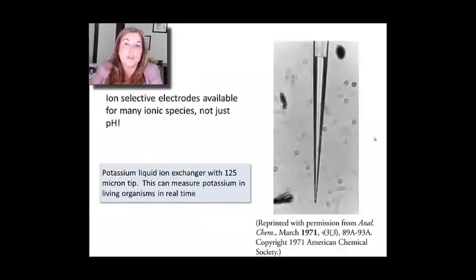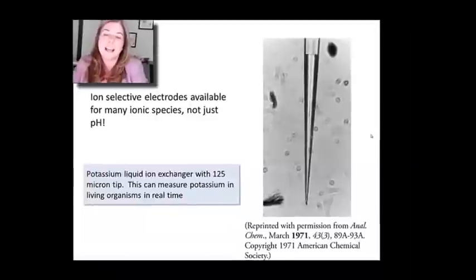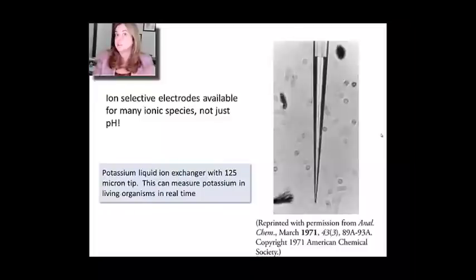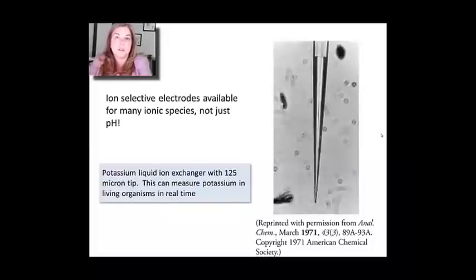Now, ion-selective electrodes, as I said, don't just have to be for pH. They can be for a lot of different things. In this case, this is a potassium ion exchange electrode, and it's very small. And so, that allows it to interact or measure, for example, potassium through tissue at very specific places. It's a little too big to do the single-cell measurements like I showed you in the last lecture. It's 125 micron tip. But, nevertheless, it can be pretty accurate in its measure of potassium. So, it's really great for electrophysiology studies, for example, in the muscles.